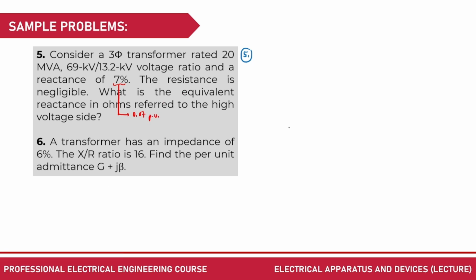Okay? So now we can use this. Referred to the high voltage side, the actual Z is Z per unit times Z base. The Z per unit is 0.07 times the Z base, which is from the higher voltage, 69,000 volts squared all over 20 megavolt ampere. So the actual Z becomes 0.07 times that, which is 16.664 ohms. This is in ohms. So this becomes our answer for number 5.